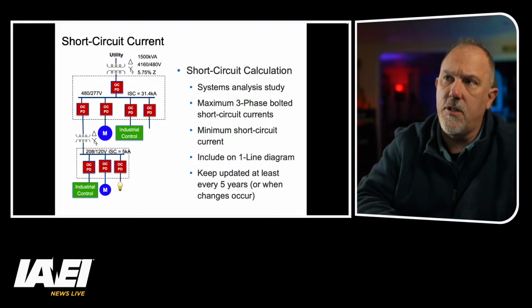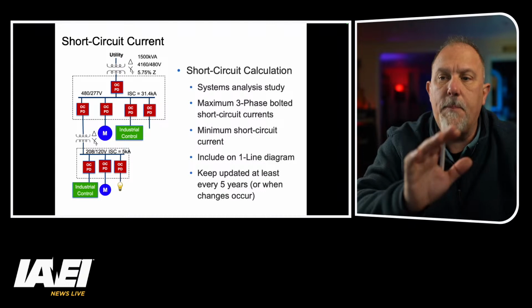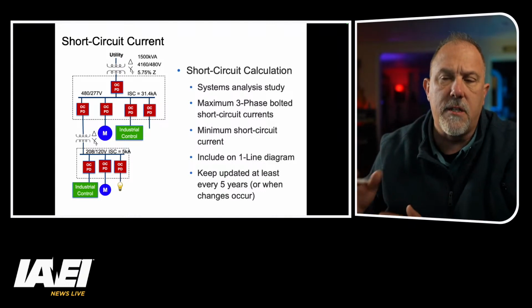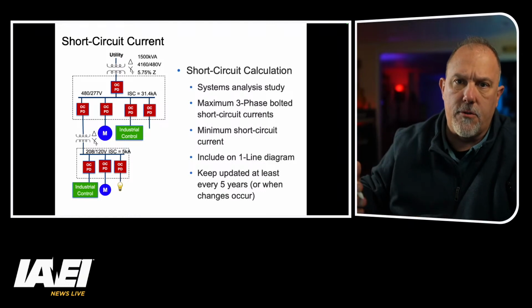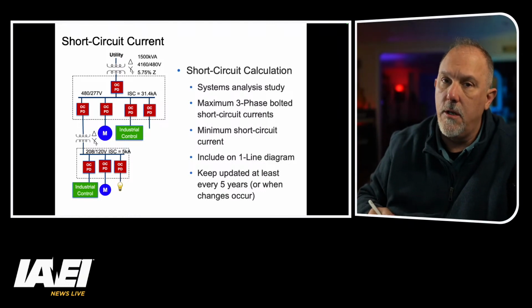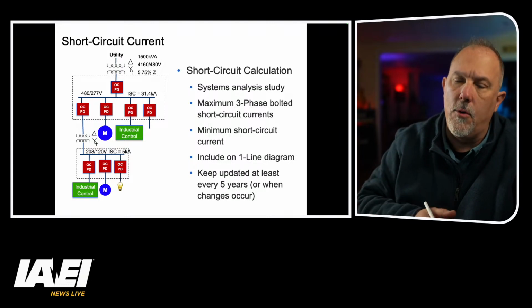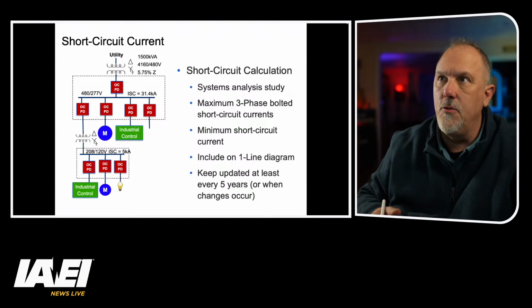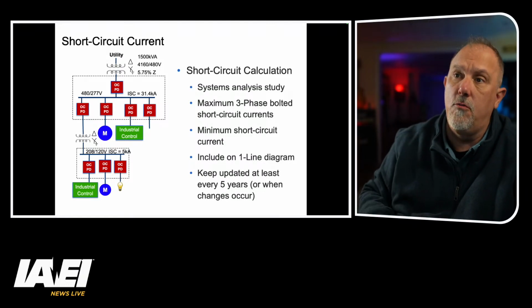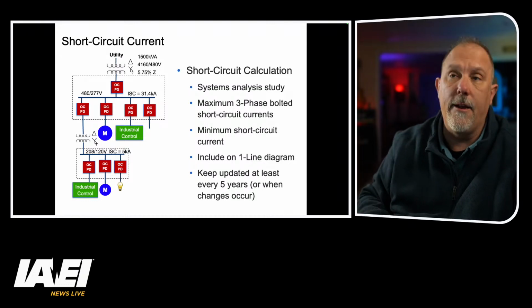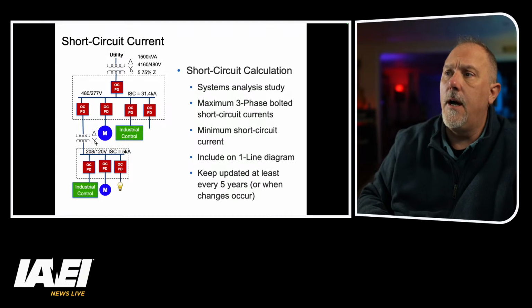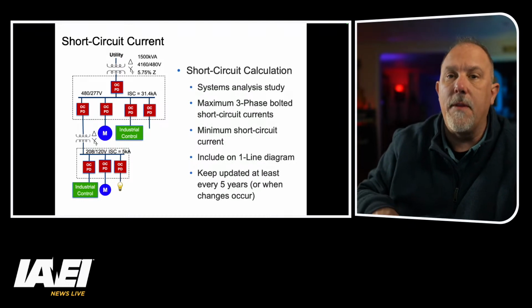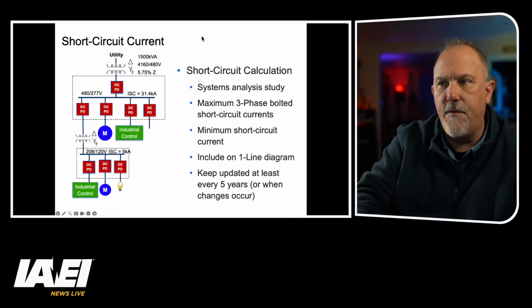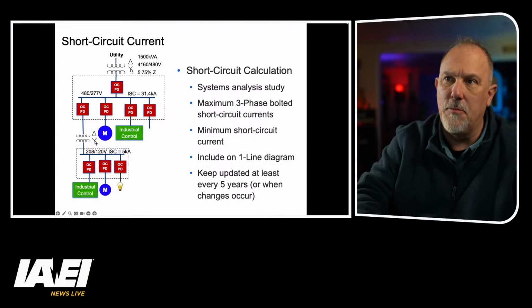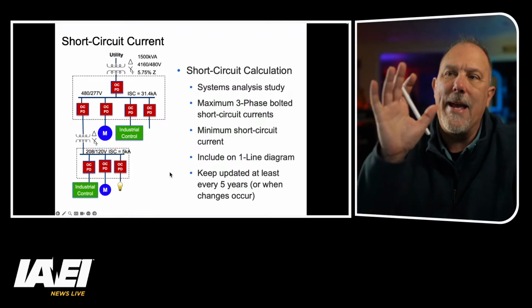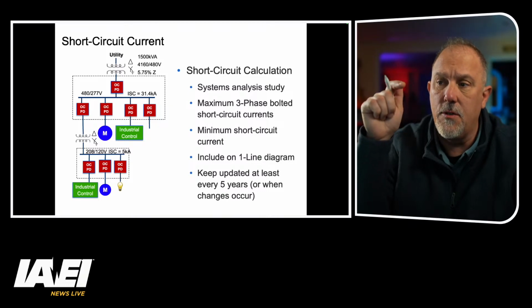Now, the power distribution system. What we would typically do for equipment evaluations is we want the maximum available fault current. So we'll make some assumptions. We'll assume that the transformer is at its lowest possible impedance. We'll assume that all of the sources are on. We will assume all of those motors are on and running. Okay? Because we want the maximum available fault current that could possibly flow in the power distribution system.